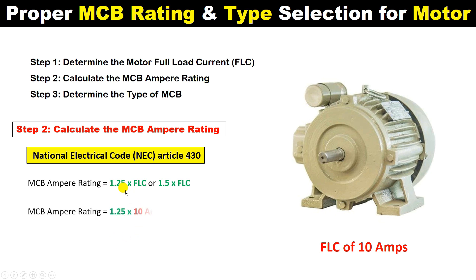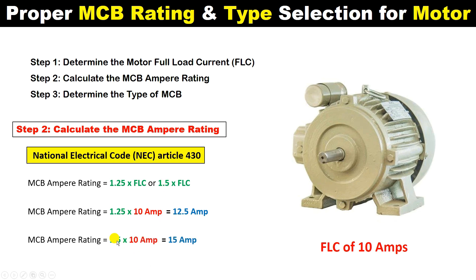Now we will multiply 1.25 with 10 ampere, which gives us 12.5 ampere. If you use 1.5 instead, then 1.5 multiplied by 10 ampere gives 15 ampere. So you have two options — you can use an MCB of 12.5 ampere or an MCB of 15 ampere.